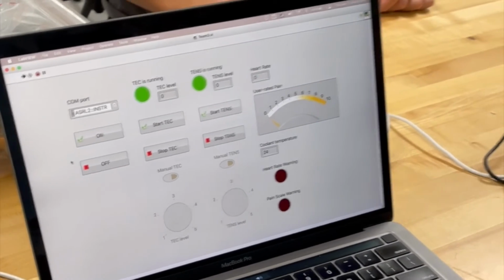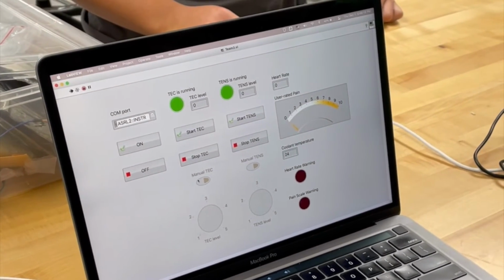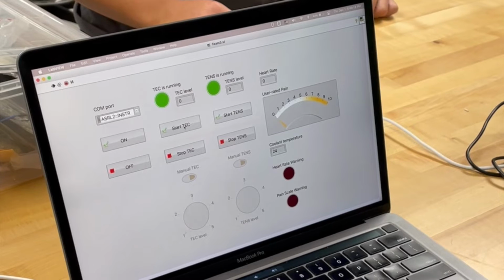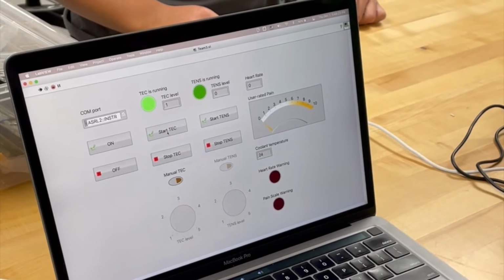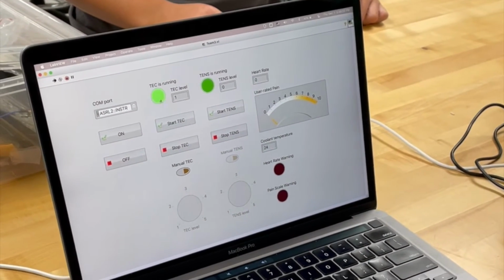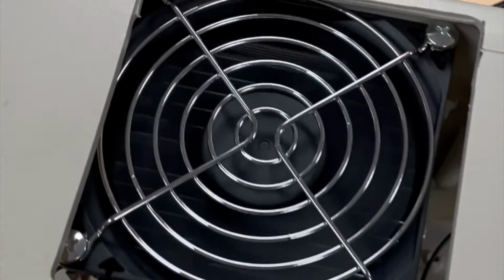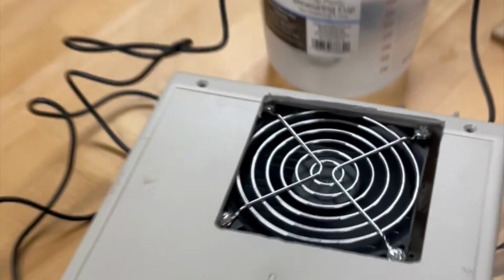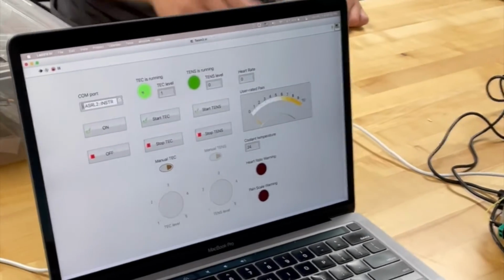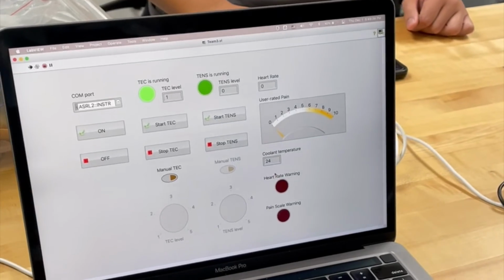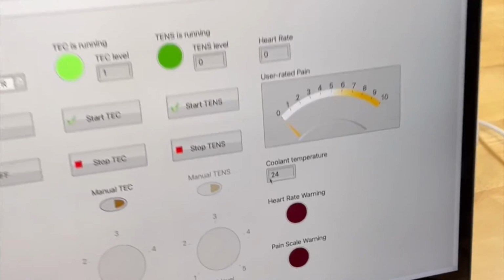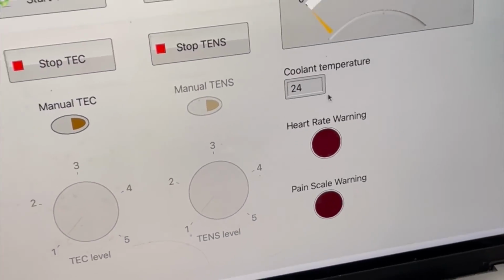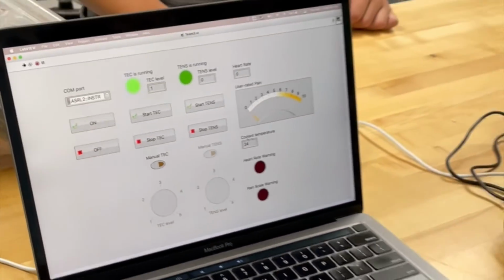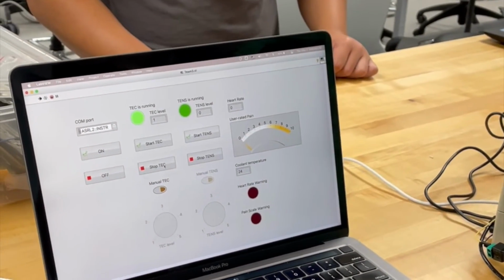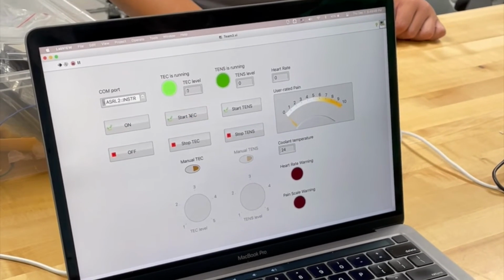We can start by turning on the device by pressing the on button, which communicates with the device to start sending data to LabVIEW. We have the option to turn on the thermoelectric cooler, which turns on the light to indicate that the thermoelectric cooler is on, and the fan started going off, which is going to start cooling the water. We can show the picture right now. So when we started, before we started the thermoelectric cooler, the coolant temperature is being read at 24 degrees Celsius, and over time this should go down. We have the option of turning off the thermoelectric cooler and turning it back on.